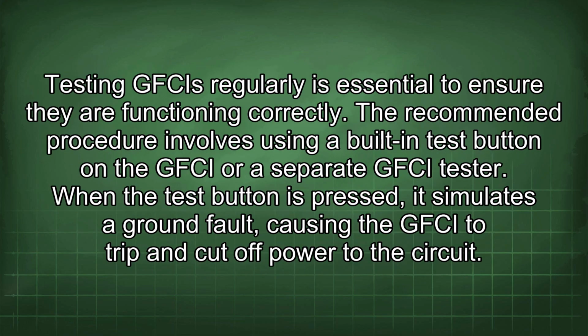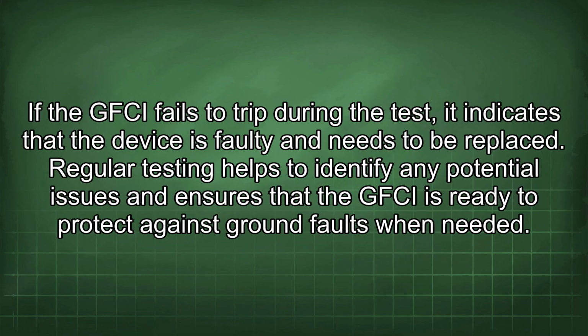Testing GFCIs regularly is essential to ensure they are functioning correctly. The recommended procedure involves using a built-in test button on the GFCI or a separate GFCI tester. When the test button is pressed, it simulates a ground fault, causing the GFCI to trip and cut off power to the circuit. If the GFCI fails to trip during the test, it indicates that the device is faulty and needs to be replaced. Regular testing helps to identify any potential issues and ensures that the GFCI is ready to protect against ground faults when needed.